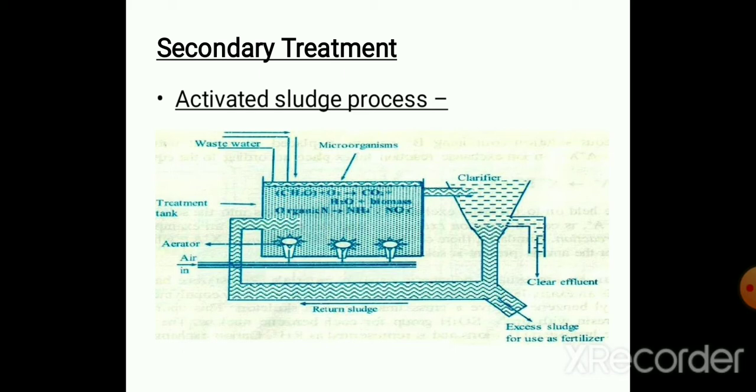So in this process, sedimented sewage water is mixed with a proper quantity of activated sludge. Here you can see the wastewater is passed, and here is the activated sludge, and this mixture is sent to the aeration tank in this case, in which the mixture is aerated and agitated for several hours. During this process, organic matter is oxidized in the presence of these microorganisms.